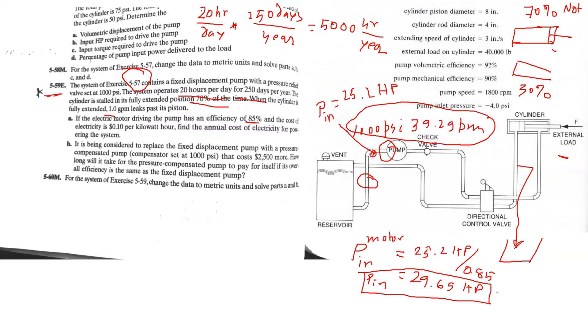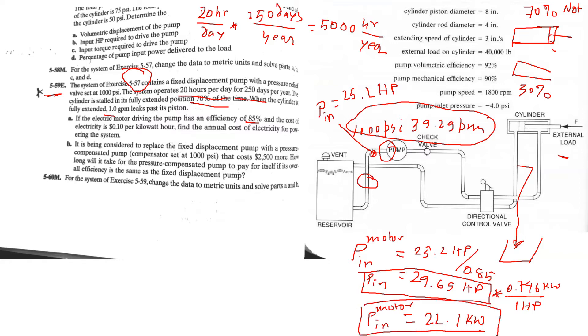Electric power is measured in kilowatts, and electricity cost is calculated based on kilowatt-hours — how many kilowatts are consumed per hour. We convert using the fact that 1 horsepower equals 0.746 kilowatts. So the motor input of 29.65 horsepower converts to 22.1 kilowatts. Whether the system is working or not, this is the amount of power the motor draws.